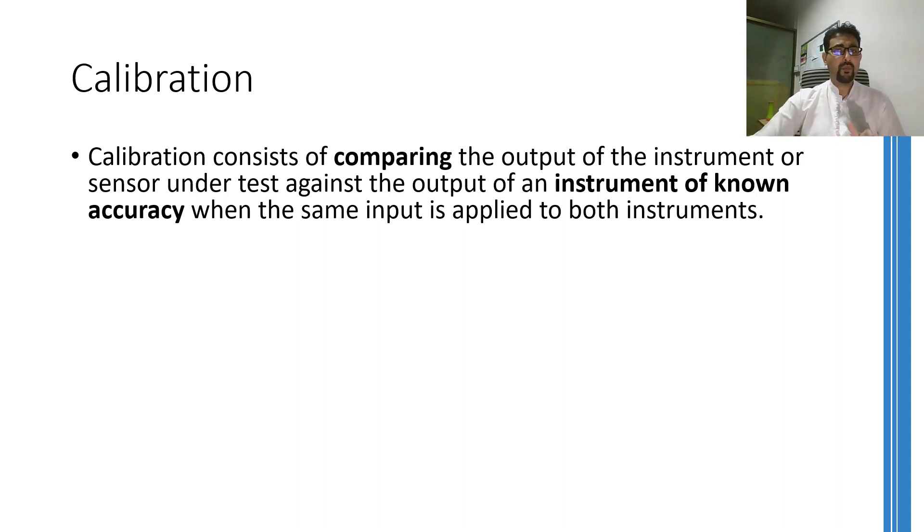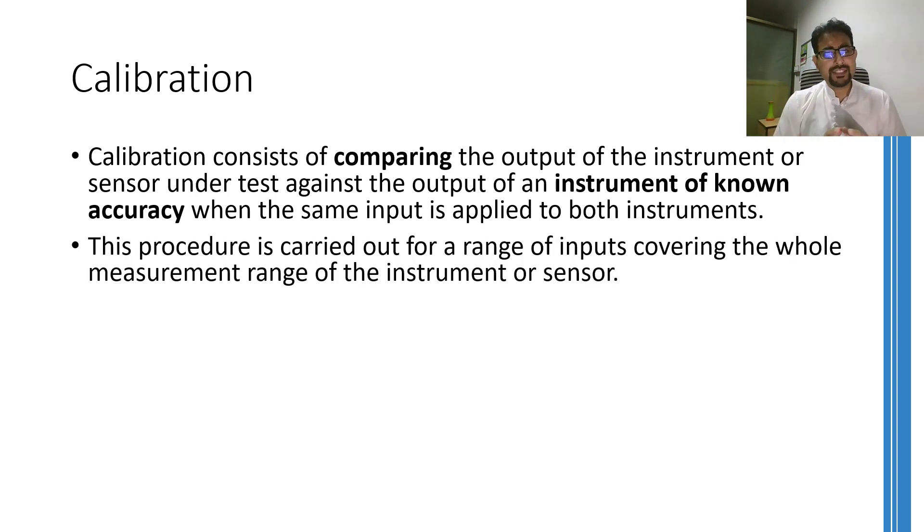If the instrument which you have installed in the factory floor shows some deviation, then it means that it needs calibration. However, if both outputs are similar or the deviation is acceptable, then the instrument can work for a bit longer. Therefore, the procedure of calibration is carried out for the whole range of inputs. It might be the case where the instrument is performing well for a certain portion of the range, but it might not be generating standard output for some other range. Therefore, when you want to check any instrument for calibration, make sure you check the whole range of the input.